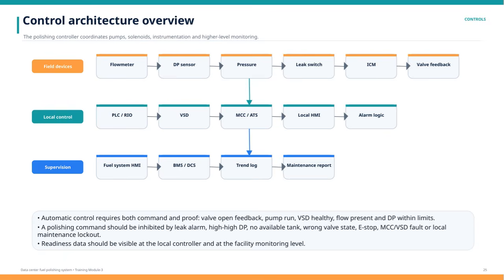It's critical that automatic control relies on both command signals and proof signals, such as confirming valve positions, pump operation, VSD health, flow presence, and differential pressure within limits. Additionally, polishing commands must be inhibited if certain fault conditions occur, like leak alarms, excessively high pressure differentials, tank unavailability, incorrect valve states, emergency stops, MCC or VSD faults, or when local maintenance lockouts are active.